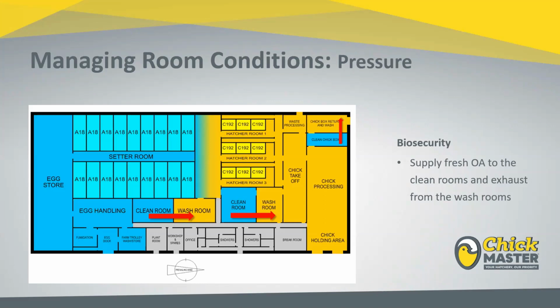Yeah, so due to the temperature that you're controlling most egg stores at, it completely depends on the atmosphere. If you're in a very dry climate where there's very little atmospheric humidity available, again, due to the lack of air exchange in an egg store, it does require some humidity, but not a tremendous amount, because we're not setting up an exchange of thousands of CFM.